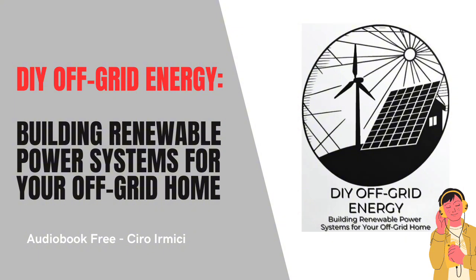For lead-acid batteries, regular maintenance includes checking the electrolyte levels, ensuring proper ventilation, and performing equalization charges to balance the cells. Electrolyte levels can drop over time due to evaporation or charging, and low levels can damage the battery's plates, reducing capacity and lifespan. Adding distilled water as needed and keeping the batteries in a well-ventilated area helps maintain optimal performance. Equalization charging helps prevent sulfation, a common issue where sulfate crystals form on the plates, impairing the battery's ability to hold a charge.